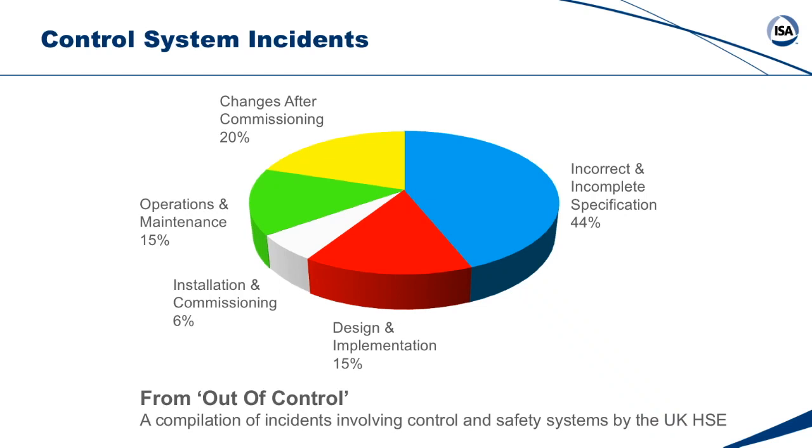And because we've had various accidents around the world, regulations have changed around the world. In the U.S., we have the OSHA, Occupational Safety and Health Administration, PSM, Process Safety Management Regulation of Highly Hazardous Chemicals, that came out in 1992 because of a number of serious accidents we had in the U.S., and this affects any facility with 10,000 pounds or more of flammable combustible materials. And that regulation says you must follow industry standards.